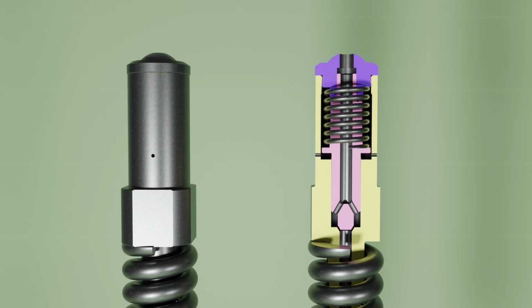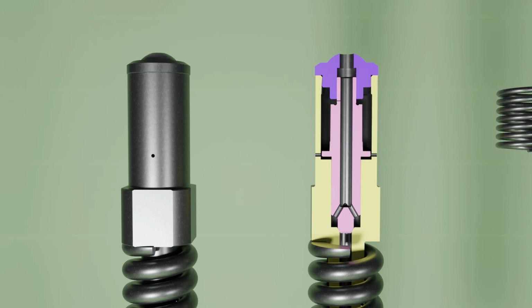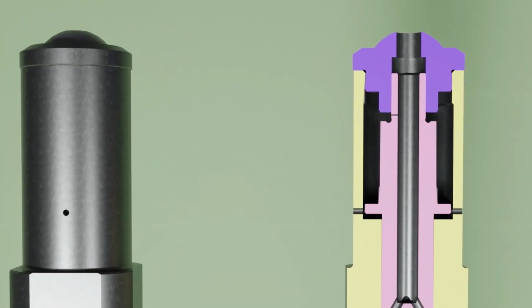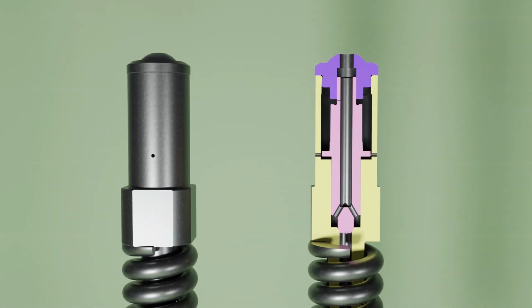Here you can see how the vent slide moves inside the non-return valve. The force of the spring acts on the vent slide, keeping it pressed against the seat. Now if we remove the spring for the sake of demonstration, you can see that the recirculation hole in the vent slide is covered by the thrust piece when it's lifted, and uncovered when it's seated back on the body. Also notice the hole on the non-return valve body, through which recirculated oil flows into the holder.